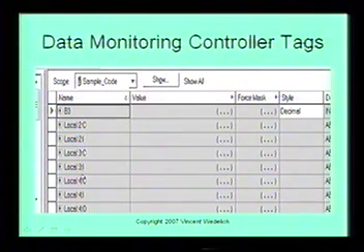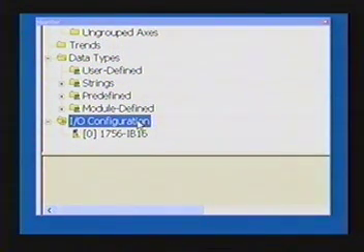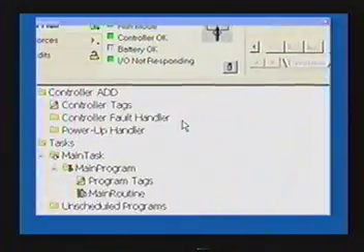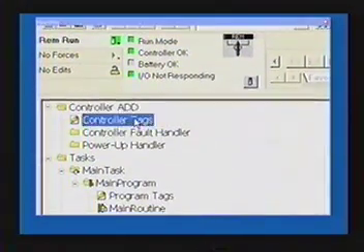So you can look at that as well, and you can see how we have an output card here as well. So we have slot 4, you have an output, an input, and a configuration associated with that. So what I did behind the scenes here is I added a card in slot 0, a 1756 IB16. The reason I did this is so that you could see a controller tag, because we previously did not have a controller tag.